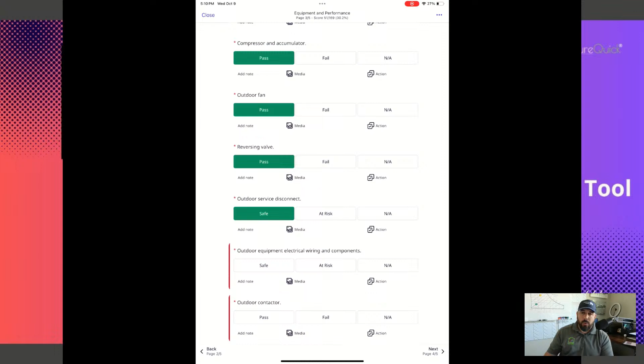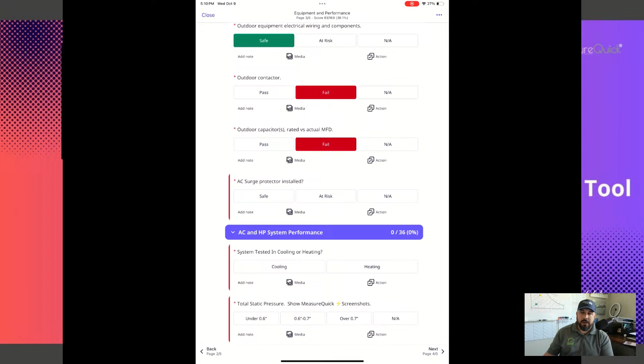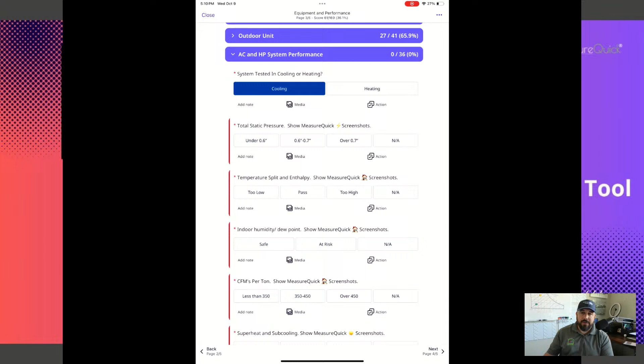Then we move out to the outdoor unit and do a refrigerant acid test. That's built into my pricing — I do a refrigerant acid test when I go out there, because it gives us insight on the system itself and the refrigerant, since maybe it's run hot for a long time and some acid has developed in the system.